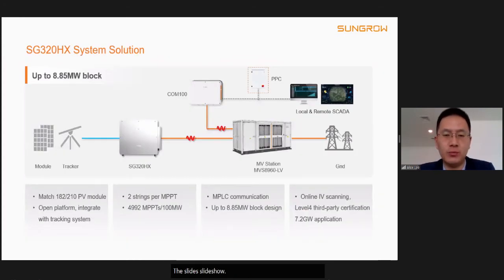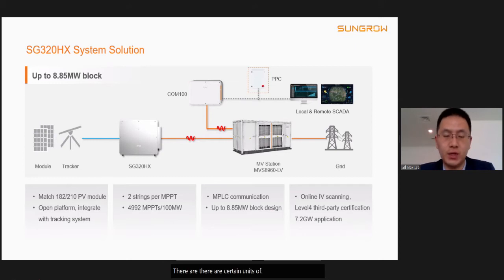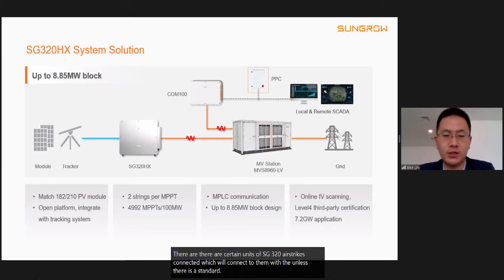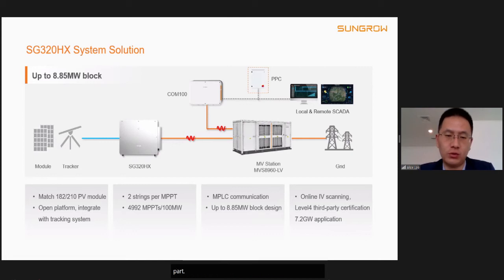This slide shows the diagram of the system solution of SG320HX in the MENA region. The block design capacity is 8.85 megawatt. There are 30 units of SG320HX connected, which will connect to the MV station. The MV station is a standard 20 feet container solution, also including the MV transformer, the RMU, the auxiliary power, and also the communication part, which is also highly integrated and saves site installation work.